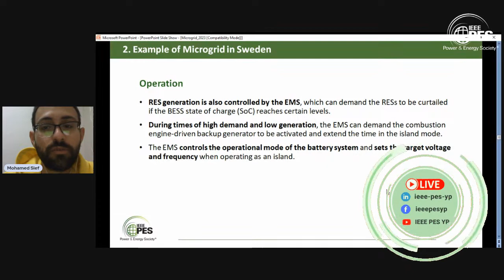Okay, the EMS, the energy management system, has direct control over the power breaker at the point of common coupling, as we mentioned before, so that it can be switched off in order to have islanding mode if we are not fulfilling the requirements of the main grid. The RES generation is also controlled by the EMS, which can demand the renewable energy sources to be curtailed, which means reduced, if the battery energy system has a high state of charge, so we need to control the generation in order to avoid overcharging, which could be harmful for the storage systems.